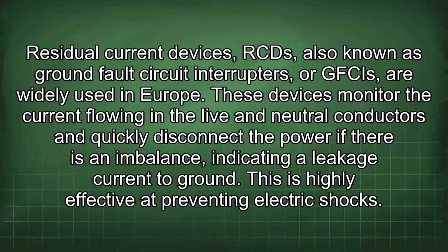Residual current devices, RCDs, also known as ground fault circuit interrupters, or GFCIs, are widely used in Europe. These devices monitor the current flowing in the live and neutral conductors and quickly disconnect the power if there is an imbalance, indicating a leakage current to ground. This is highly effective at preventing electric shocks.